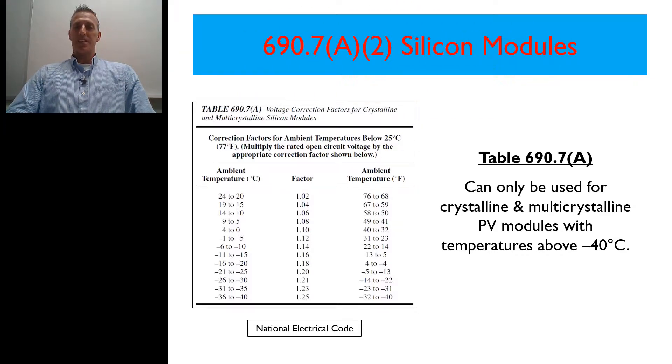In 690.7A2 of the 2017 National Electrical Code, it talks about silicon modules and using table 690.7A. One thing you want to keep in mind with this is that it can only be used when you are using crystalline or multi-crystalline PV modules that operate at temperatures above negative 40 degrees Celsius.